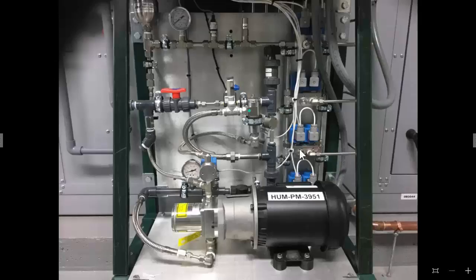So let's look at the next scenario. Say this dump valve works fine, but this zone valve stays open. It's stuck open. It is a normally closed valve and it stays open. Well, a lot of things can happen there, depending on whether you're calling or not calling, which zones are calling, and how the system is actually running. If that's the zone that was calling, say it had just come on, this one right here, zone 3, and it opens up, the dump valve closes, the system would run along fine, no problem. And if you continued to have zone 3 on and running fine, and you just called for another zone, it would still continue to operate properly.